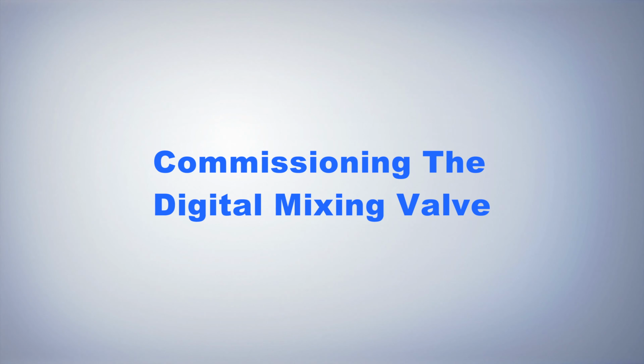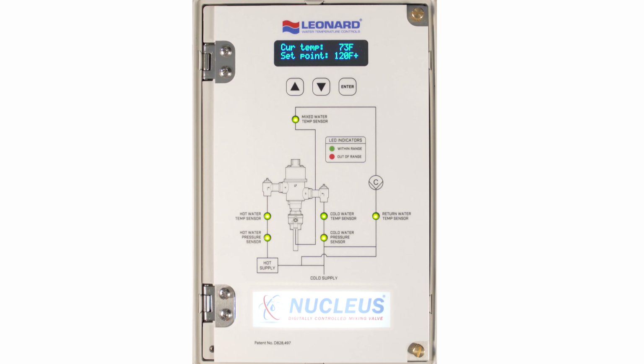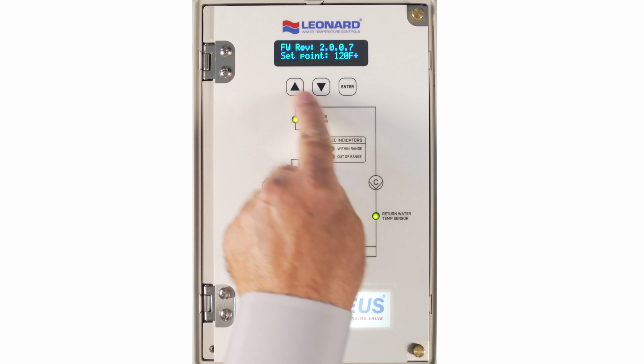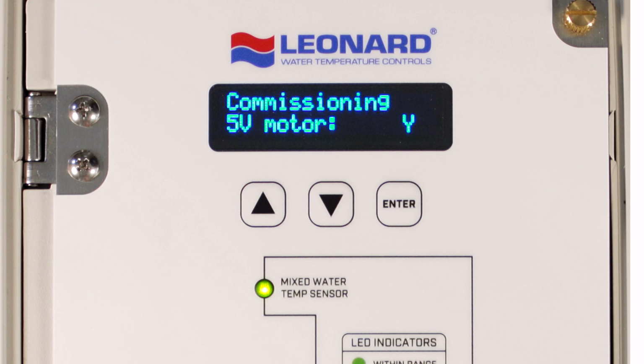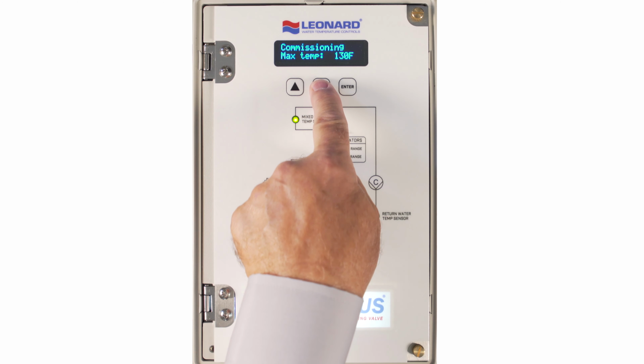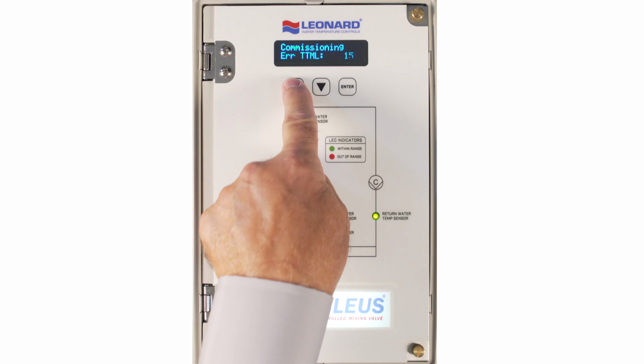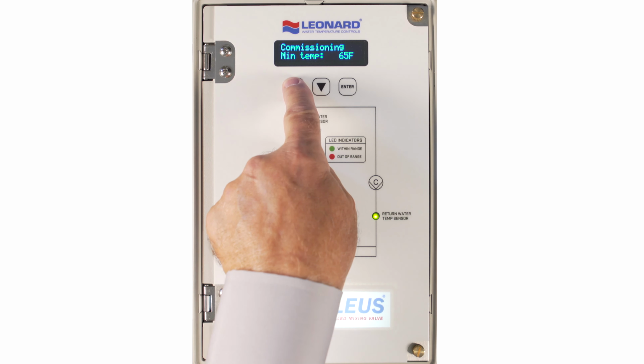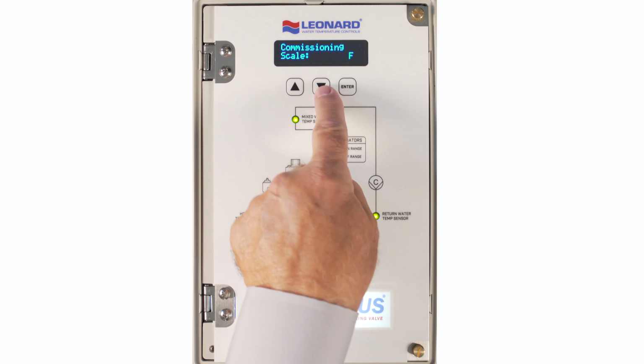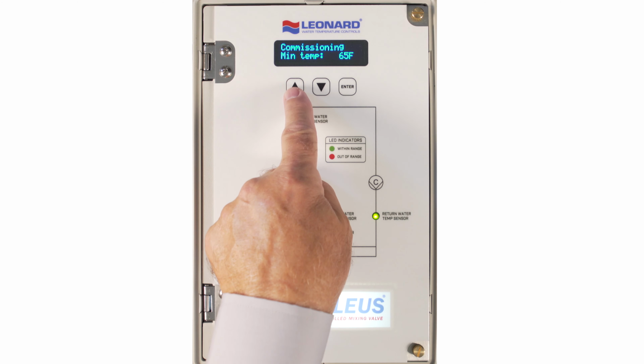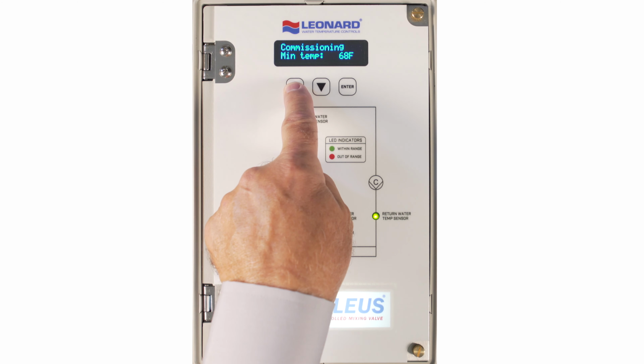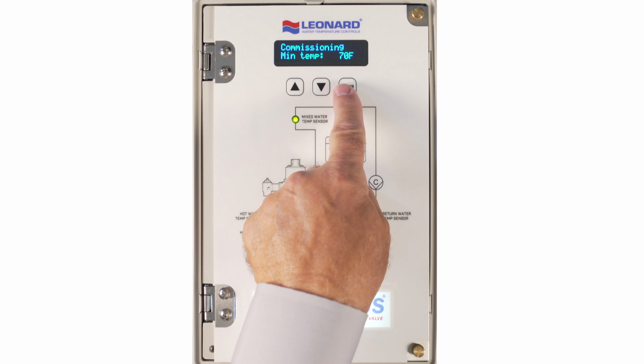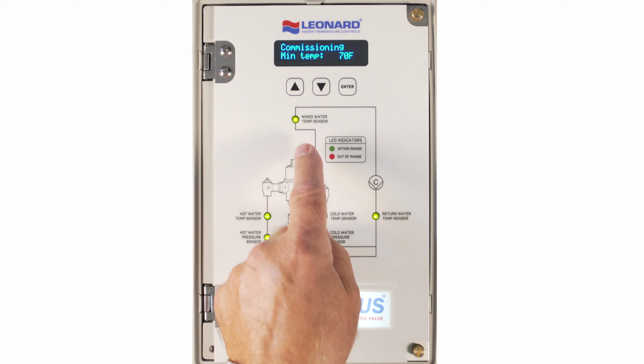Commissioning the digital mixing valve. To enter the commission menu via the panel, push the keys in the following sequence: up, down, enter. Now in commissioning mode, use the up or down keys to scroll through the various adjustable parameters and set points. At each screen, pressing the enter key causes the default value to flash, and the value shown can now be changed using the up or down keys. Once the desired value is displayed, pressing enter locks in the new value.